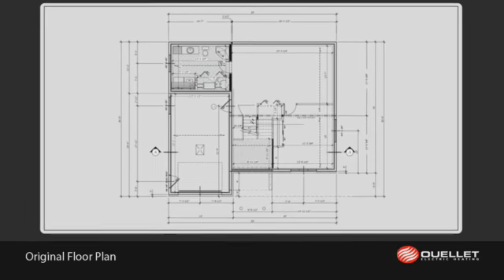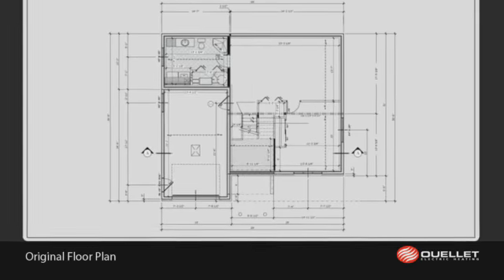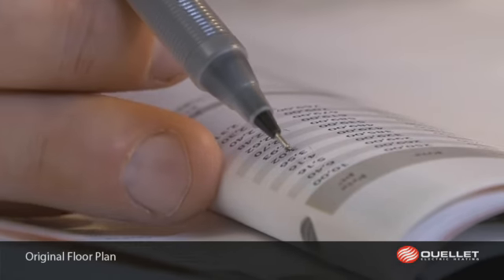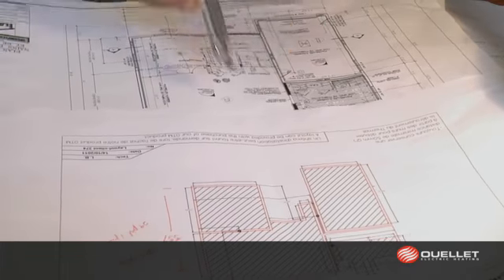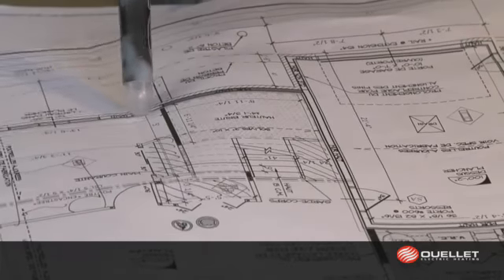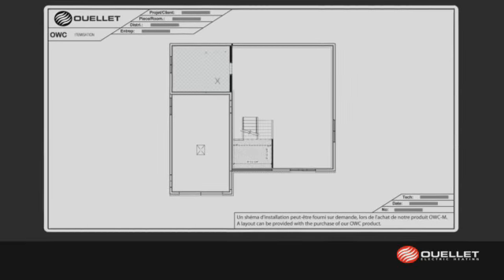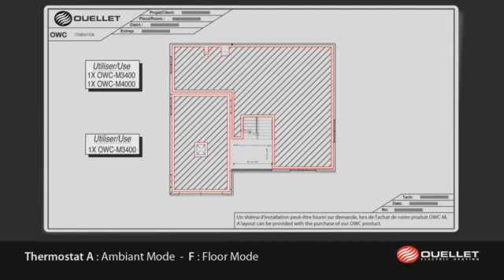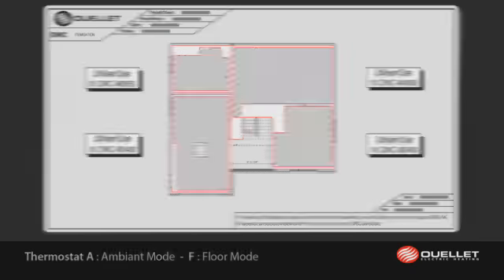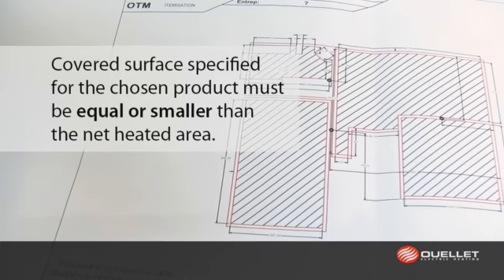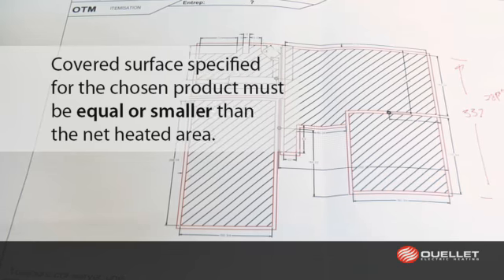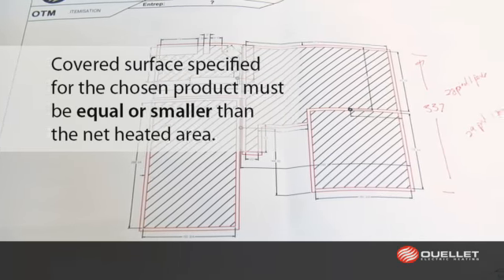In order to choose the proper mat or reel size, you must first estimate the areas to be heated. With a floor plan to scale, Ouellet can assist you during this step by offering an estimation service. The heating cable for concrete allows you to do surfaced and zoned heating. Make sure the thermostat is set appropriately. It's important that the covered surface specified for the chosen product be equal or smaller to the net heated area.